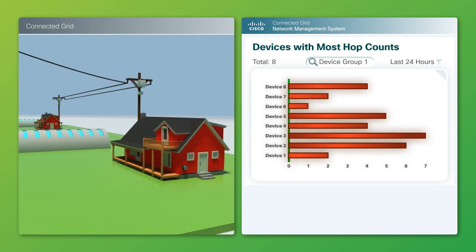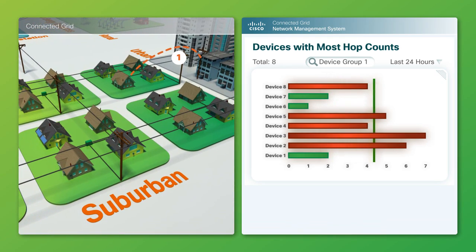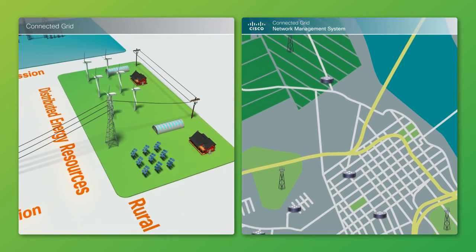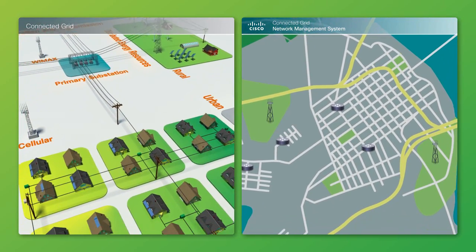For example, a rural smart meter network may be designed to operate optimally with no more than two hops away from a pole-top router, whereas an urban smart meter might operate optimally up to five hops to pole-top routers. Cisco CGNMS can be customized to proactively alert utility operators in real time to suit each utility's operational needs and geographic terrain.